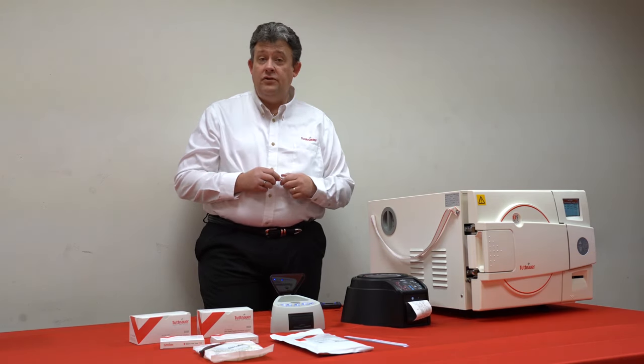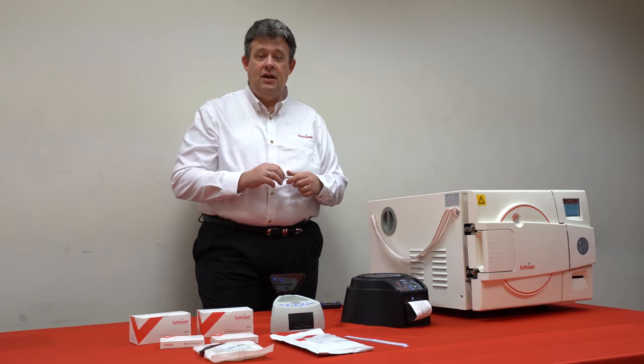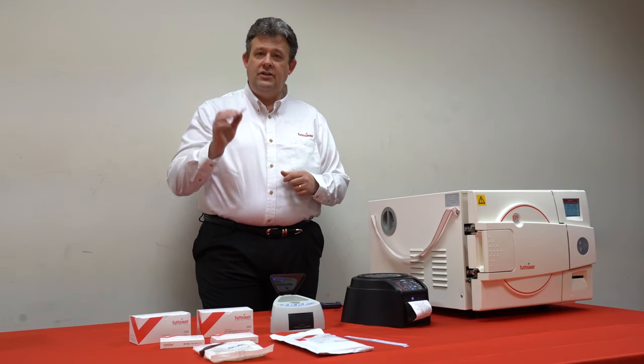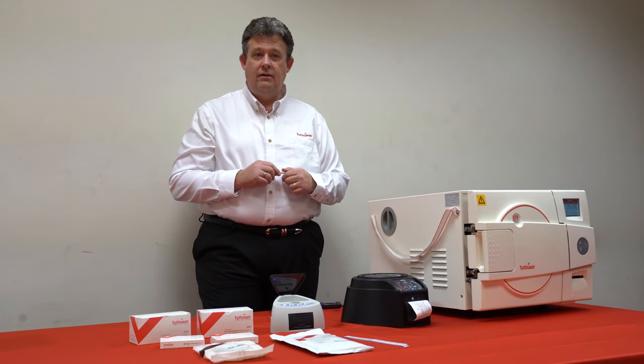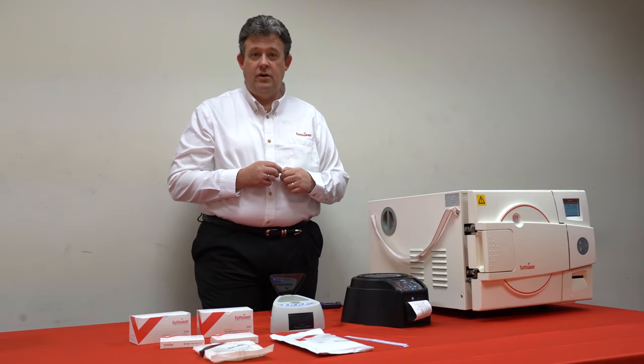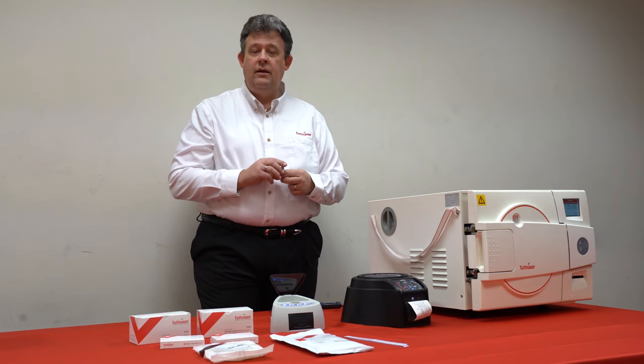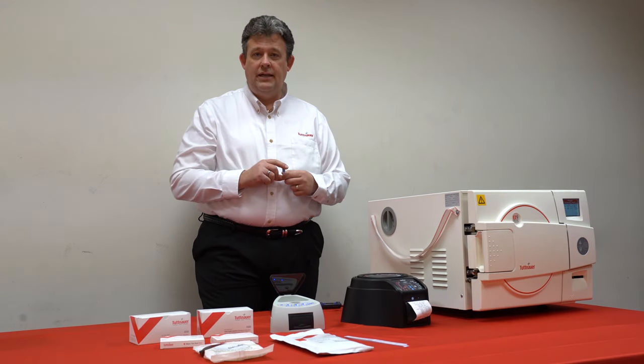As far as how to use them, they should be used on a cycle-by-cycle basis — in other words, every cycle that they run, they should have a biological indicator in there. The reason being is how do we know our sterilizer is working from one cycle to the next? The only way we can ensure that is by using a biological indicator.